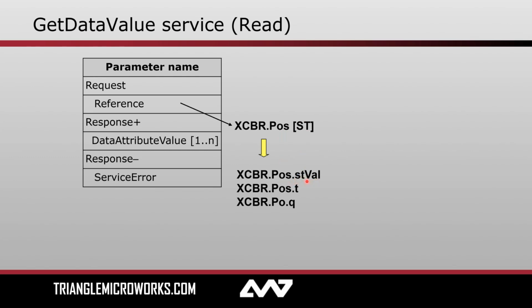So this would include things like the stVal to let us know the actual position of the breaker, but also the t, or timestamp value, which lets us know the last time that breaker operated, opened, or closed. And then finally the q, or quality, which lets us know, is there any reason I shouldn't trust this data? Are you as the server aware of any issues with the integrity of the data?